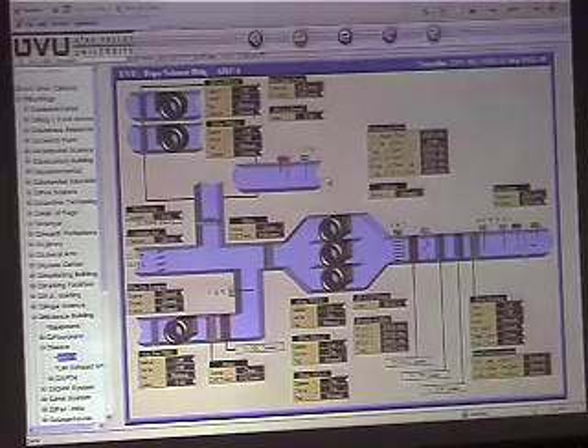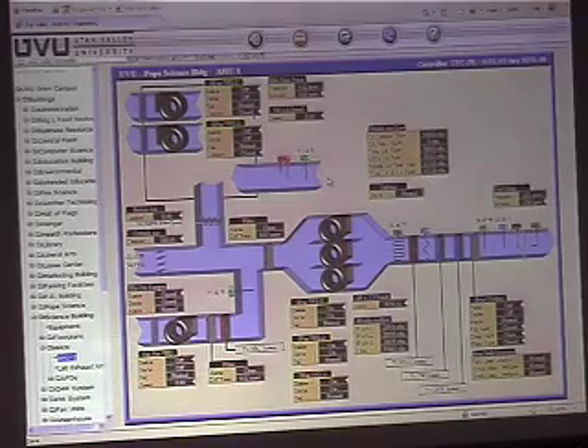Where are the points that we're monitoring from as far as floors and for building static? They are located, I believe there's 4 different corners of the outside of the building that we're monitoring, off of level 0. When we get up there, I can look on the mechanical drawings. They've got them drawn out where the tips are located. Is there just one duct static pressure transmitter or sensor location? Yeah, and it's located down here on this level.